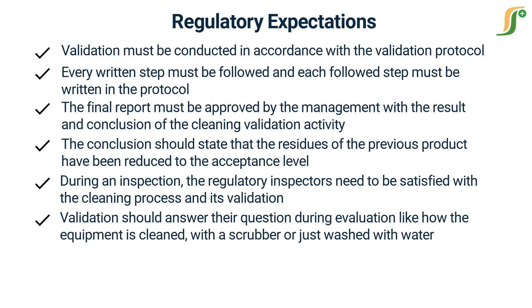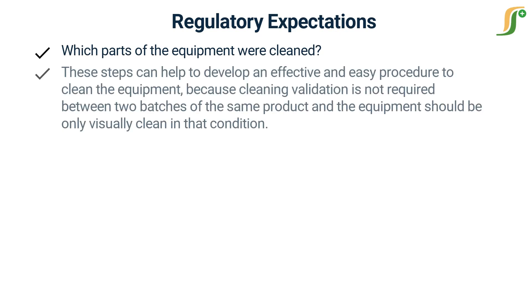Validation should answer questions such as: how is the equipment cleaned — with a scrubber or just washed with water? Was cleaning batch-to-batch or product-to-product? Which parts of the equipment were cleaned? These steps can help to develop an effective and easy procedure to clean the equipment, because cleaning validation is not required between two batches of the same product, and the equipment should only be visually clean in that condition.